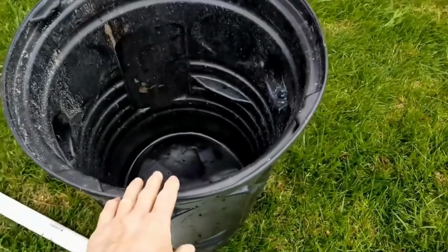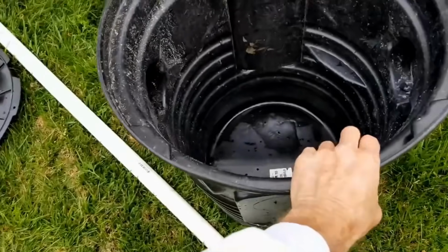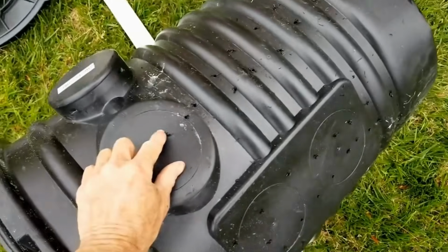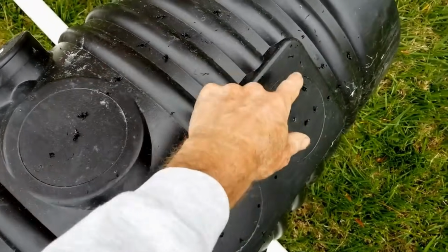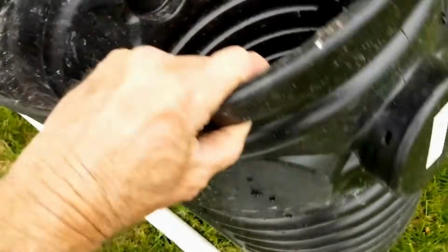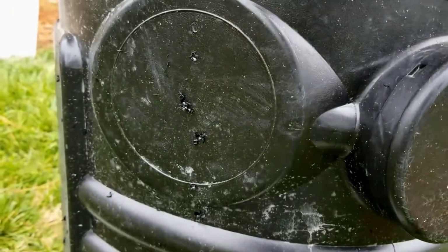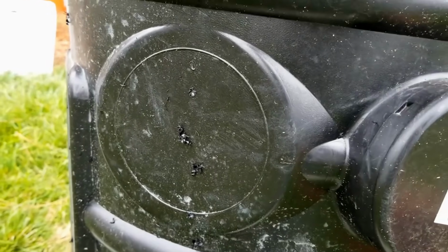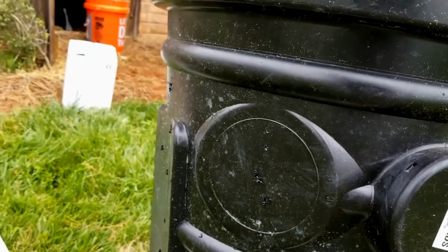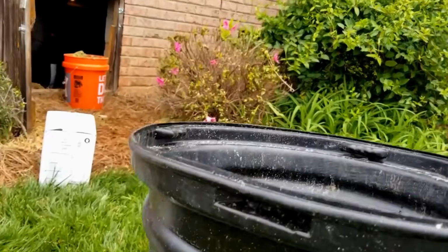Then of course you're going to need a sump basin and a sump lid. And I went ahead and perforated this. If you can see those holes, I put holes all the way around it because we want the groundwater, as it floods up and comes against the side of the basin, to be able to flood into the basin and the pump lift it up and take it out.